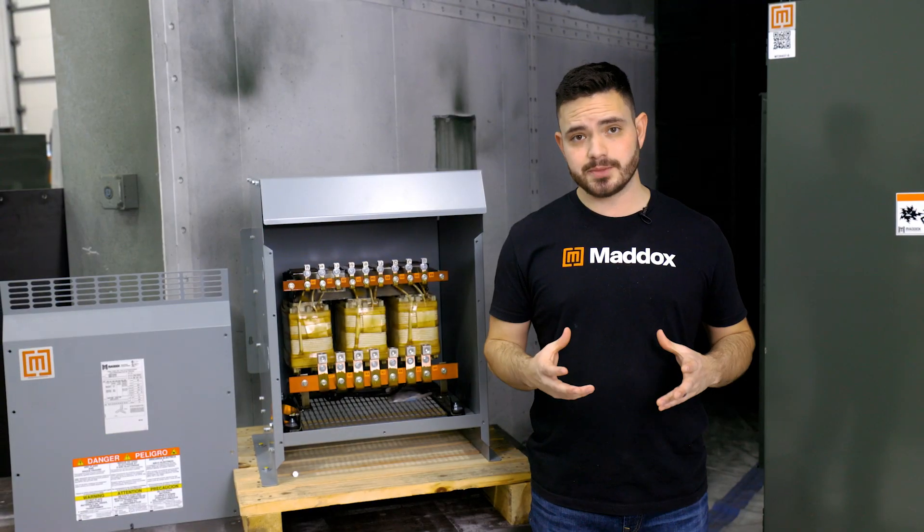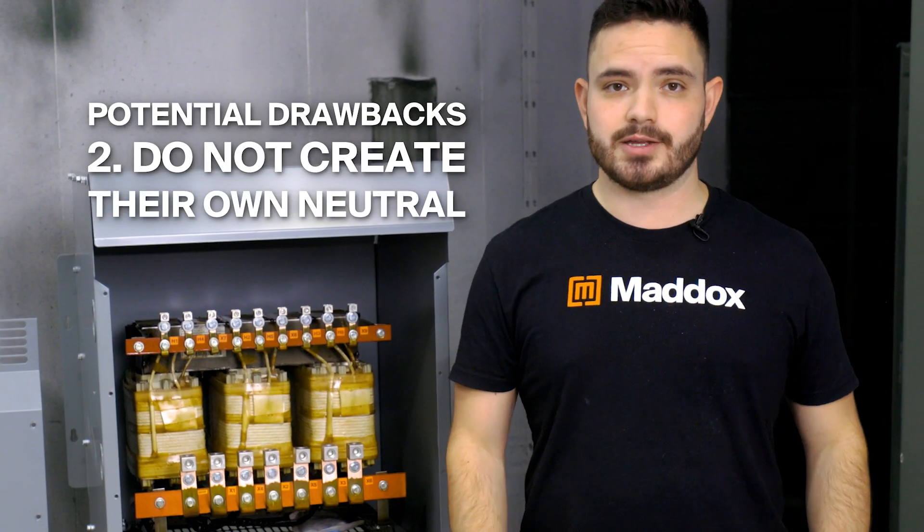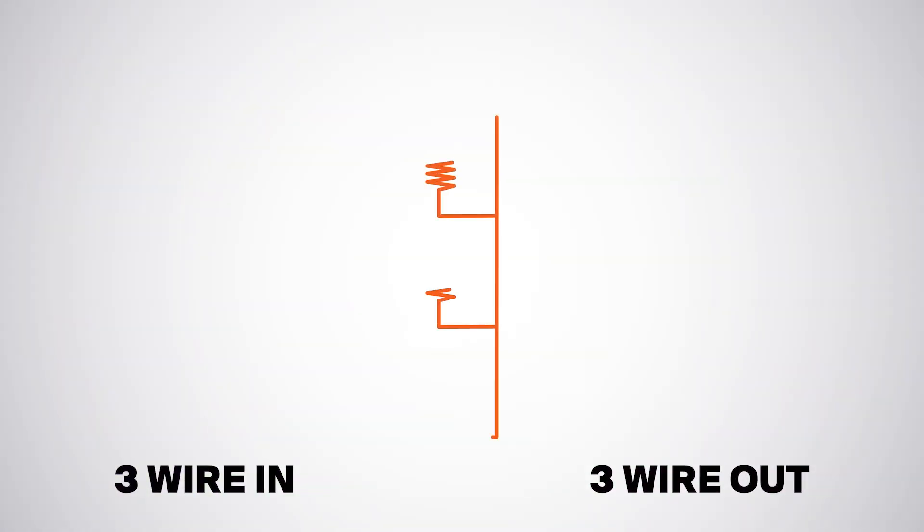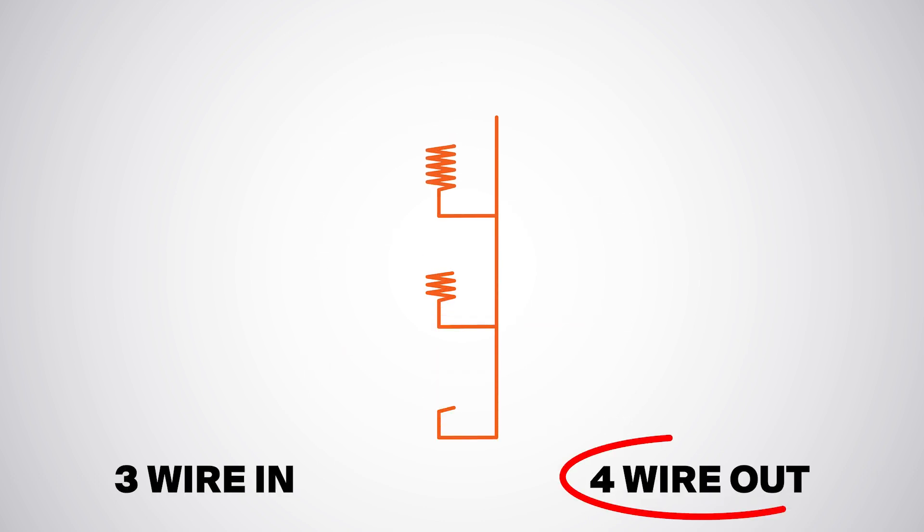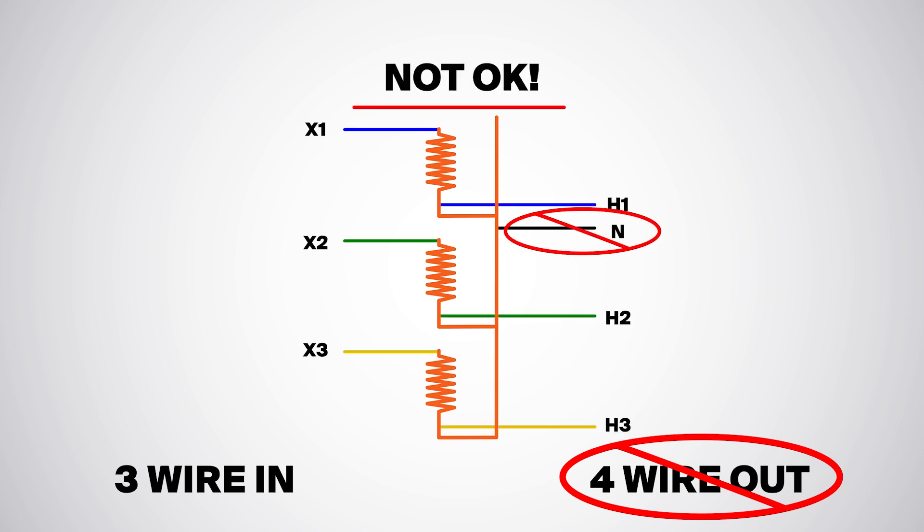Because of the lack of isolation, auto transformers do not create their own neutral. So that means three wires in, three wires out is okay. Four wires in, four wires out also okay. Four wires in, three wires out works just fine. But three wires in, four wires out does not work.